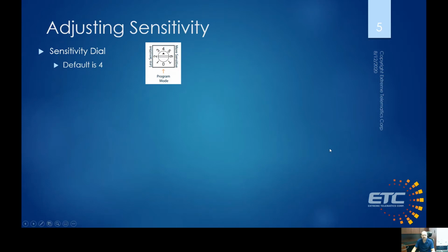So in terms of adjusting sensitivity, there is a sensitivity dial. Its default is 4, that's the middle of the road in terms of sensitivity, which sets the threshold that's required to trip. And this is on all of our sensors, and it's really to signal the arrival. So it's less to do with different types of plungers and things like that. It's more about the amount of ferrous material that's going to take to trigger the arrival, so that we don't trigger on background noise or other noise.